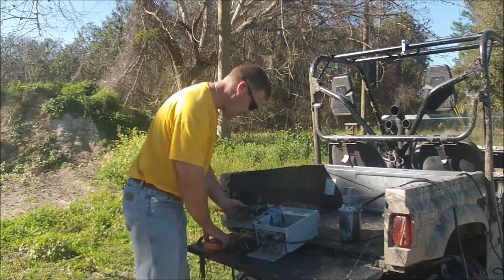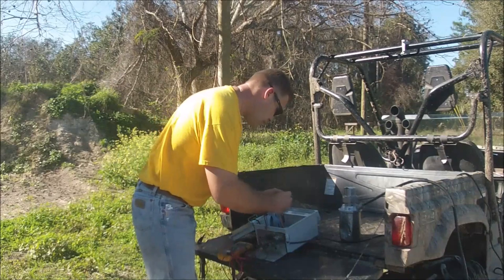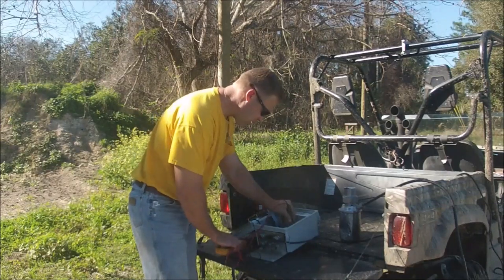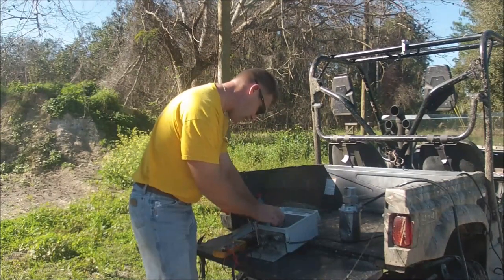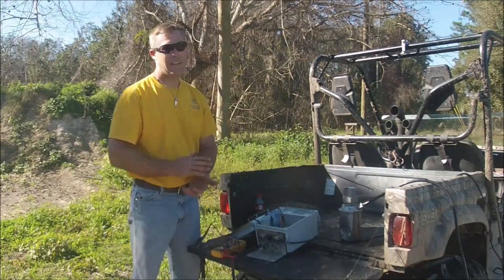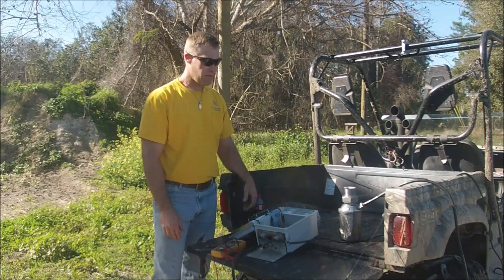The power supply's fan is on, so that's working. The light showing that the CPU is functioning is on. We've got good voltage coming out of our sensing head, so we're making a reading right now. And the 4 to 20 output is working. So we still have a functioning unit here — we just don't have a display. We know at Electron Machine that our equipment is going to get damaged in the field; that's just part of it. So we make everything field repairable. All we'll simply do is put a brand new door on it and we should be back up and running.